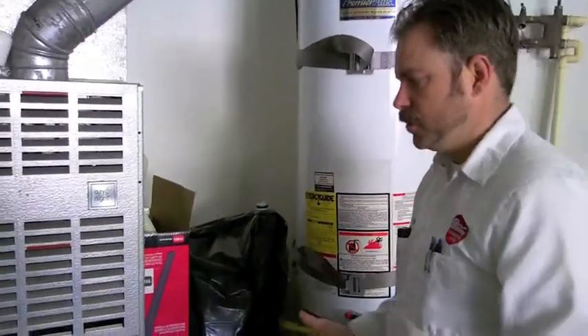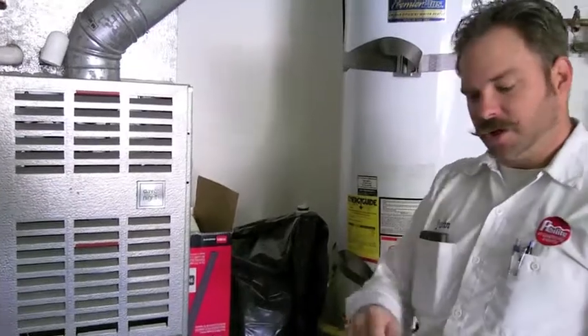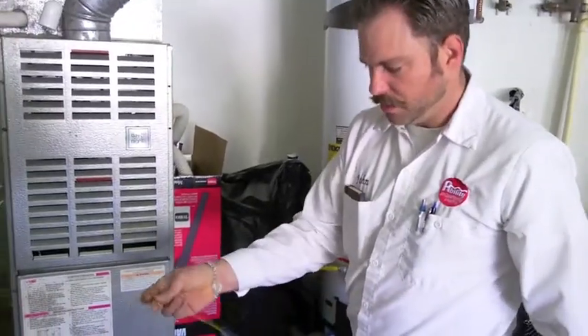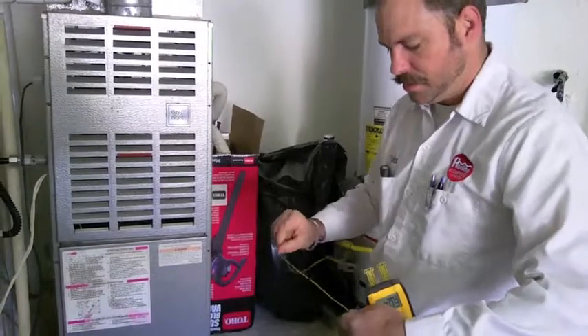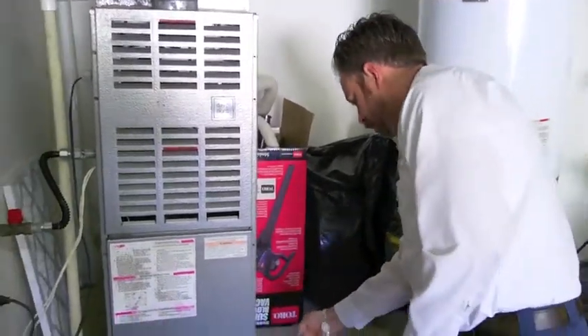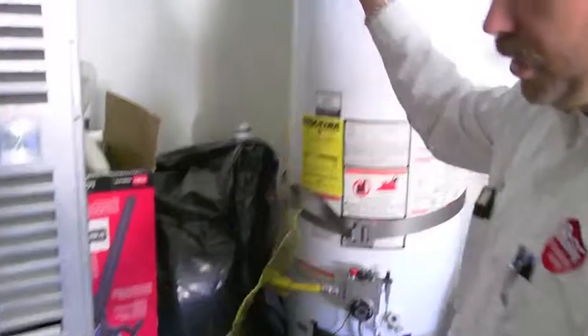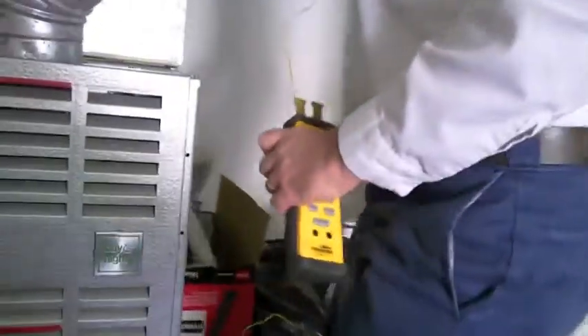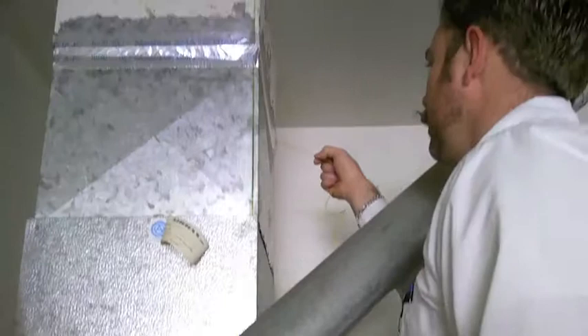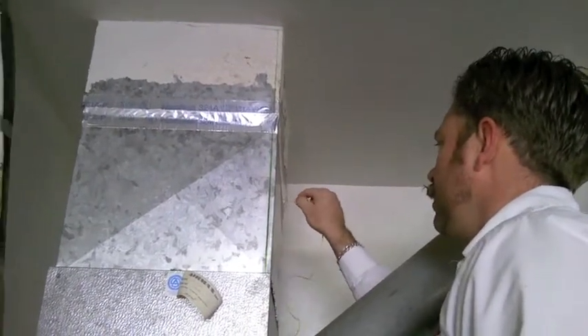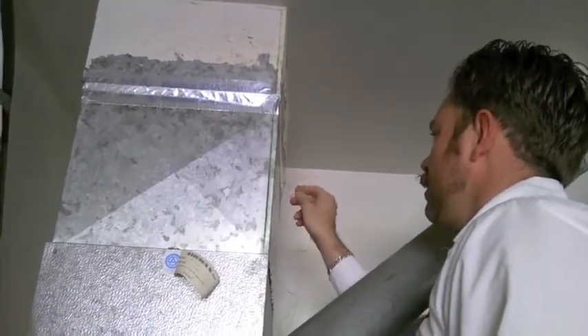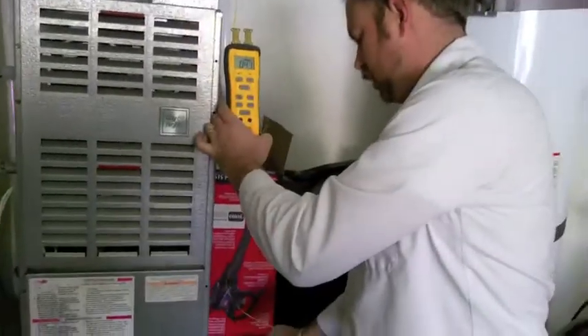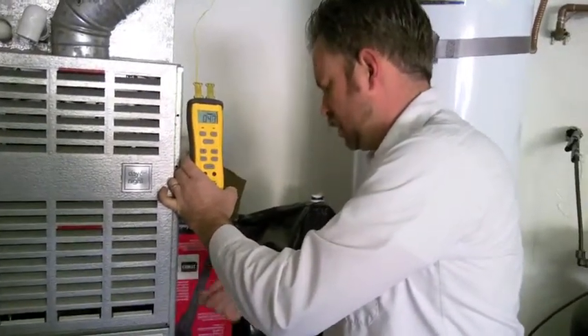So we're going to do a temperature rise measurement, which is important for furnaces. It makes sure that the furnace isn't getting too hot and basically causing cracks in the heat exchanger, which is a safety issue. One probe you want to put on the inlet of the furnace, which is the fresh air coming in. And then you want to put the other probe on the supply, and then this is going to give you a temperature difference.